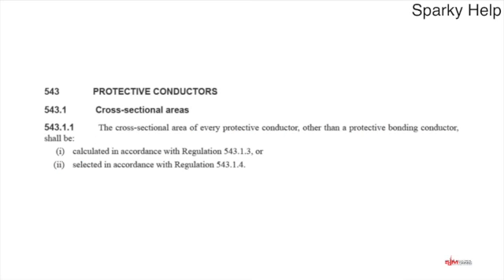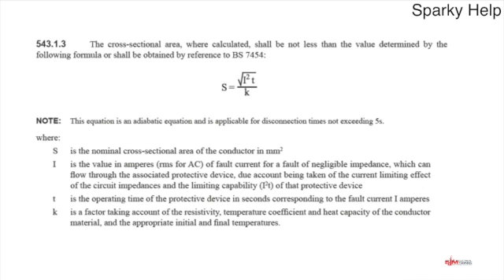Protective conductors, how do we size them? Well, there are 2 ways that our regulations actually refer to, and it says the cross-sectional area of every protective conductor other than a protective bonding conductor. Okay, so not that. This is your CPCs pretty much we're talking about, and maybe the earthing conductor as well, because it's all part of the same thing. Shall be, number 1, calculated in accordance with Regulation 543.1.3 or selected in accordance with Regulation 543.1.4. So it suggests that your protective conductors have got to meet one of those 2 requirements.